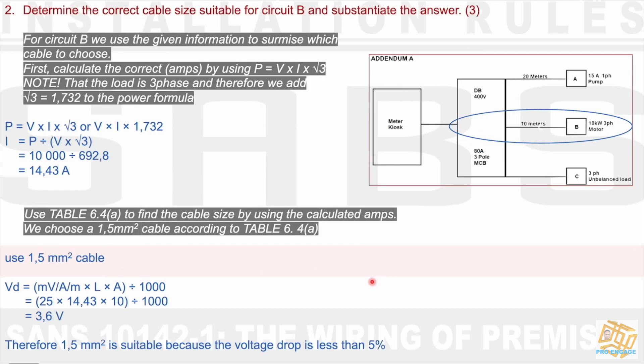Number two. For circuit B, we use the given information to surmise which cable to choose. First, calculate the correct amps by using P equals VI√3. Note that the load is in three-phase, and therefore we add √3 equals 1.732 to the power formula. P equals V times I times √3, or P can also equal to V times I times 1.732. Therefore, we manipulate the formula. We say I equals P divided by V times √3. We find the values 10,000 divided by 692.8, and we find 14.43 amps.